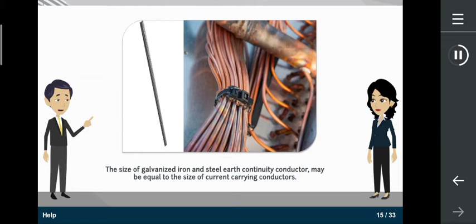All right. Further, the size of earth continuity conductor should not be less than half of the largest current carrying conductor, provided the minimum size of earth continuity conductor is not less than 1.5 mm square for copper and 2.5 mm square for aluminium, and it need not be greater than 70 mm square for copper and 120 mm square for aluminium. Regarding the size of galvanized iron and steel earth continuity conductor, they may be equal to the size of current carrying conductors.